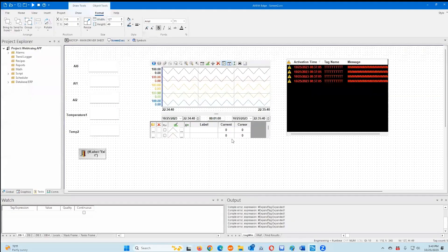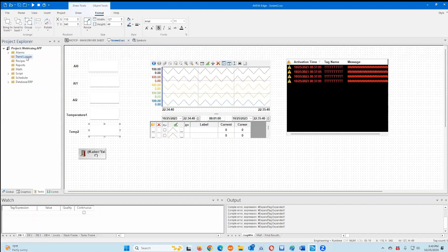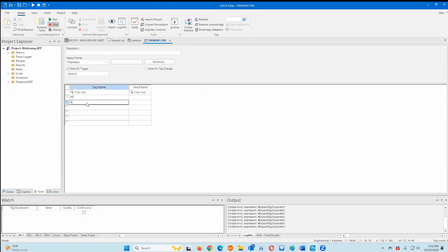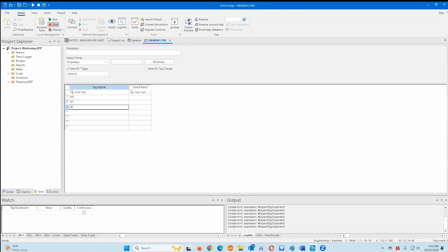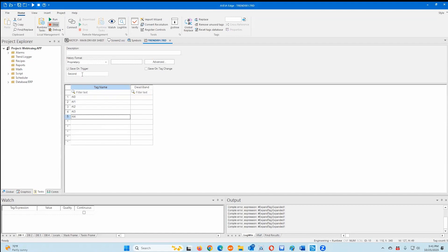The next thing I want to show you is how to do some data logging. So if we wanted to save these values to a file, first of all we go back to the project, the development project. And then also under the tasks tab we do trend logger. And we just double-click or right-click and do insert. We always have to specify the tag name that we want to do. For this one I'll do AI zero, AI one, let's do all of them. AI two, AI three, and finally AI four. For this demo we'll use it so that it uses the proprietary database and we'll save it every second. If you want, you can save it on change or save it however you want. But for this demonstration we'll just use the default which saves it every second.